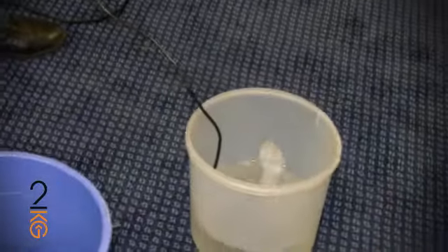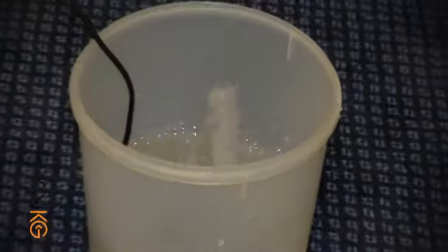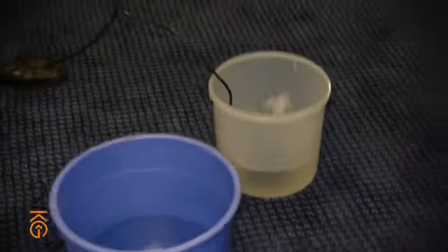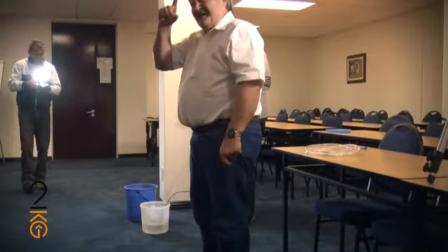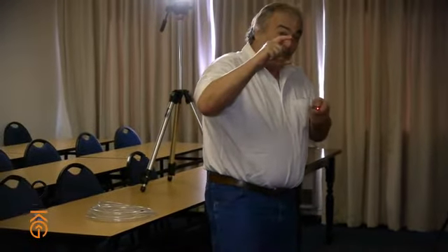Now, this is a pump. It is a little fish tank pump, but it is just like your pumps. I'm going to make this pump go into cavitation. We're going to see this pump operating all over the curve. We're going to practice various things with this pump. Now, looking up here at the board, we're out here on the curve. This pump is way out here on the curve. We've got very high flow and very little head. This is the head. You can see it right there. That is the elevation of that pump. So we're way out here on the curve.